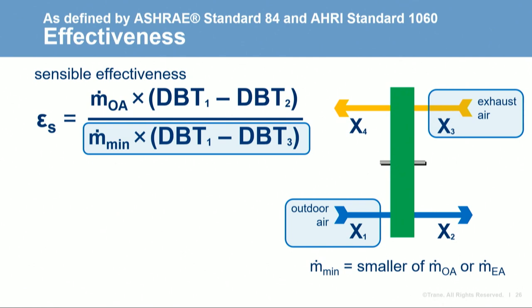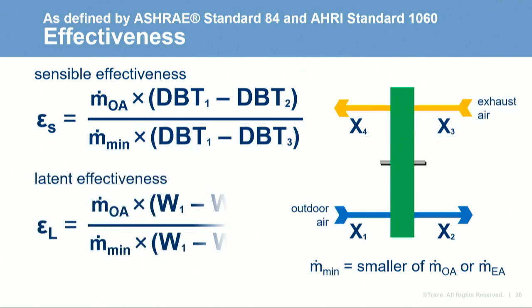Note that if the outdoor and exhaust flow rates are not equal, the maximum energy transfer is limited by the smaller of the two flow rates. The equation for calculating latent effectiveness is similar but uses humidity ratios in place of dry bulb temperatures. There's a third equation for total effectiveness that combines both sensible and latent transfer.